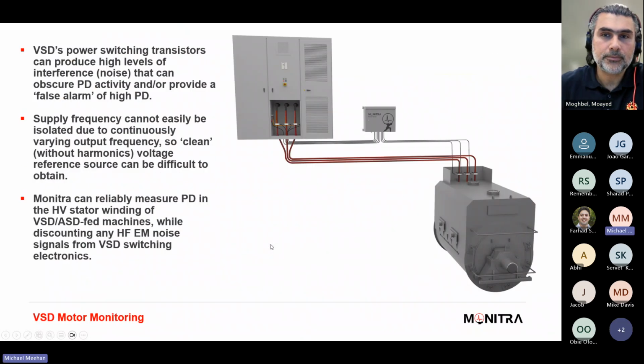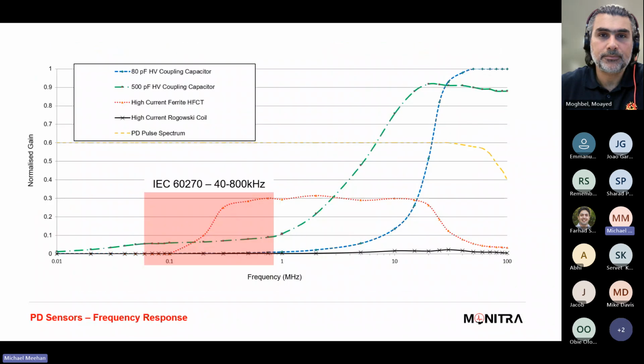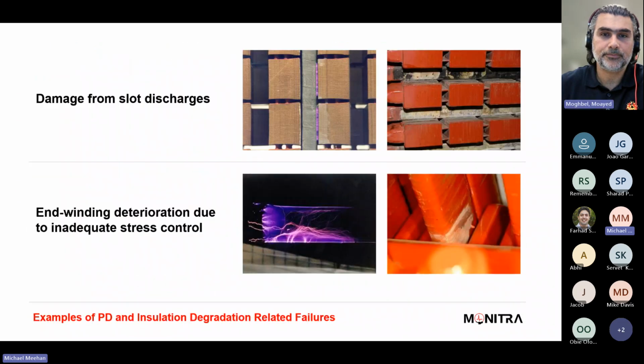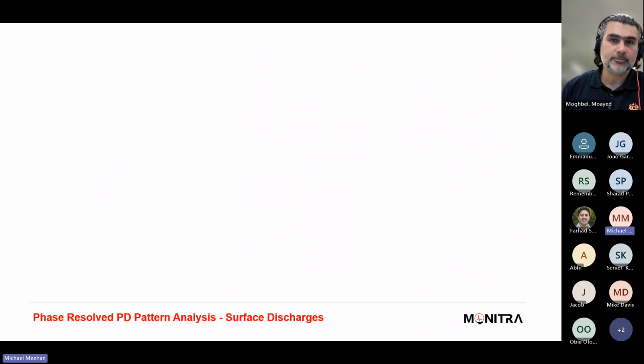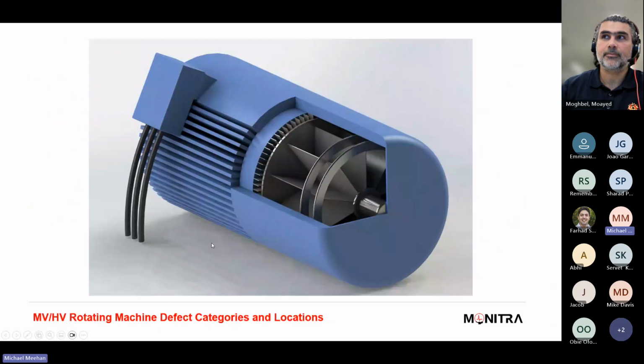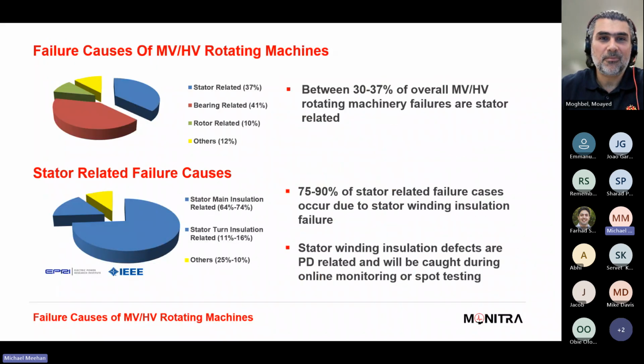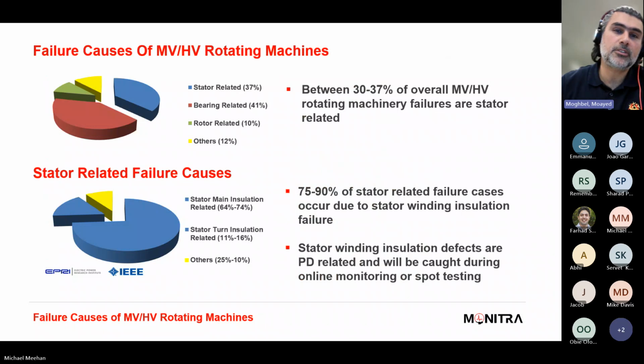Sorry, I'll go back to the failure modes slide. Maybe what I'll do is bring up the slide, and if you could repeat the question, that would be great. I think it was here. We have 40%, which is quite high, bearing related partial discharge and faults. Is that referring to the end winding, or can you give more detail on what the bearing related faults could be?